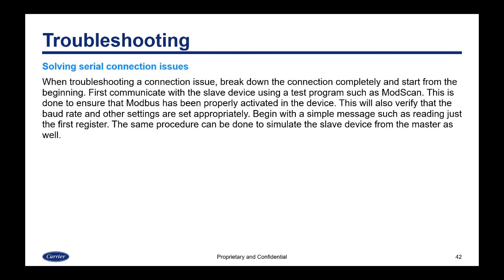When troubleshooting a connection issue, you want to break down the connection completely and start from the beginning. First, communicate with the slave device using a test program such as ModScan to ensure that Modbus has been properly activated in the device. This will also verify that the baud rate and other settings are set appropriately. Begin with a simple message such as reading just the first register. The same procedure can be done to simulate the slave device from the master as well.